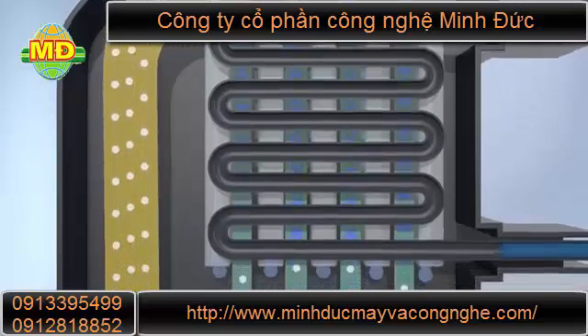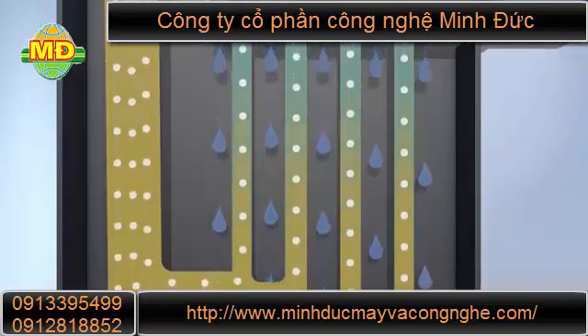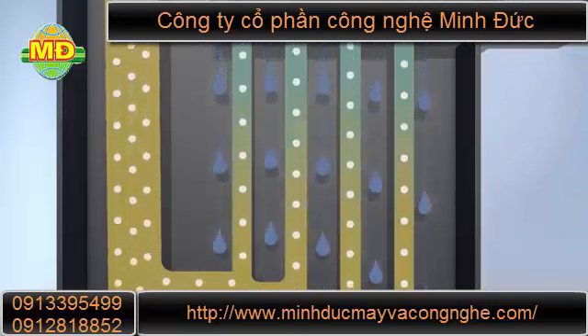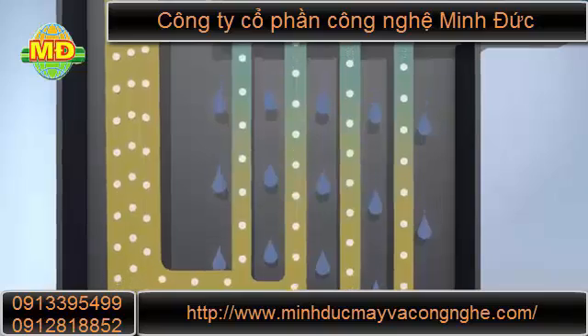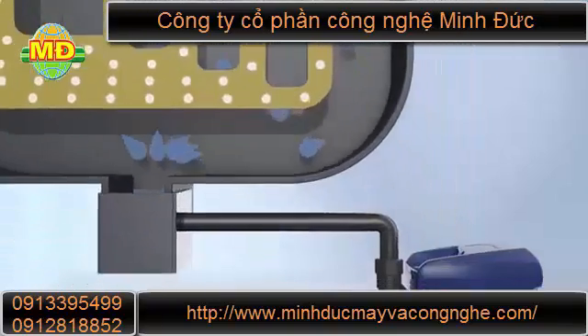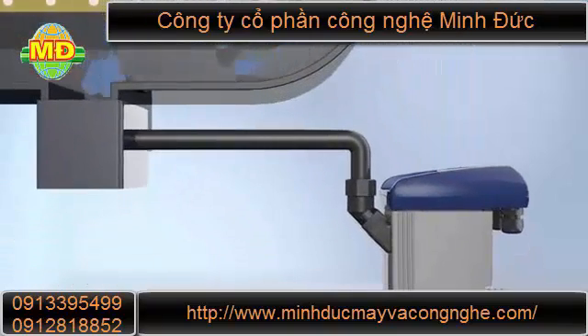The ideally dimensioned demister removes 99% of the water droplets. The condensate then simply flows into the integrated Bekomat condensate drain, and all without the loss of compressed air.